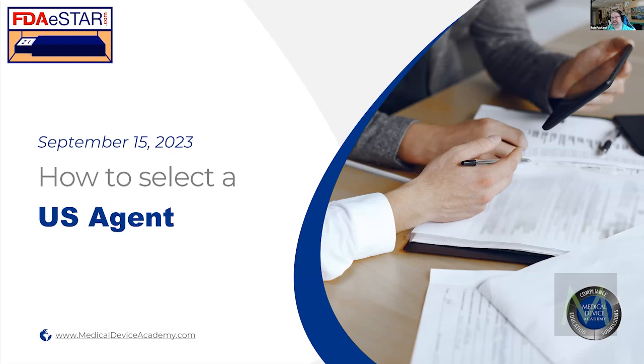October 1st, the FDA is no longer accepting 510(k) or De Novo submissions as an eCopy. You cannot submit it that way anymore. You must submit it as an eSTAR from that point forward. It's part of the modernization of the FDA, trying to go to one standard format for all submissions.